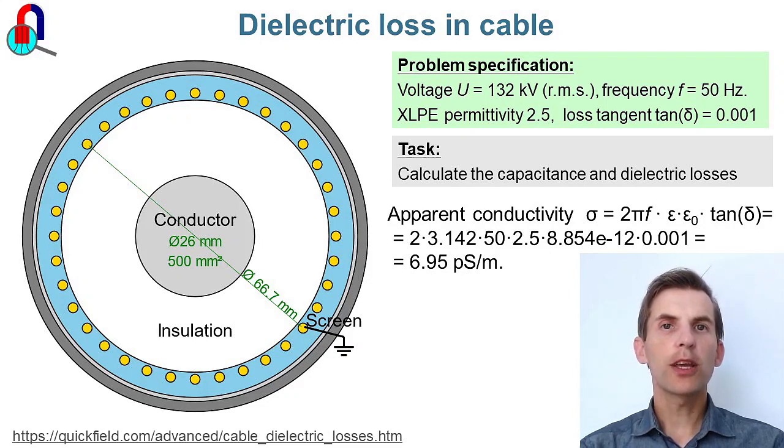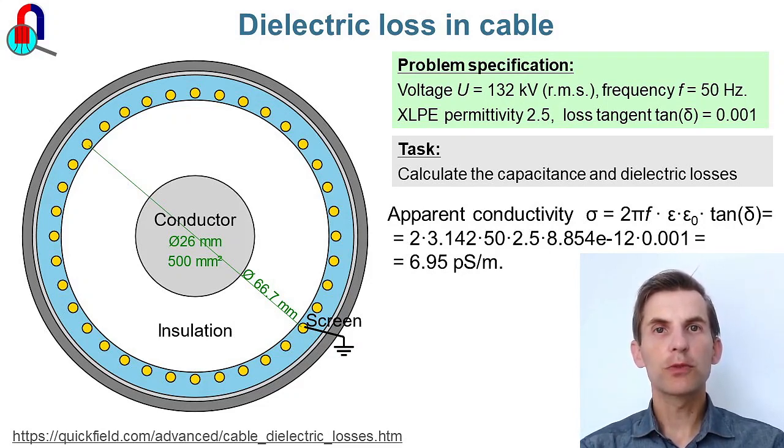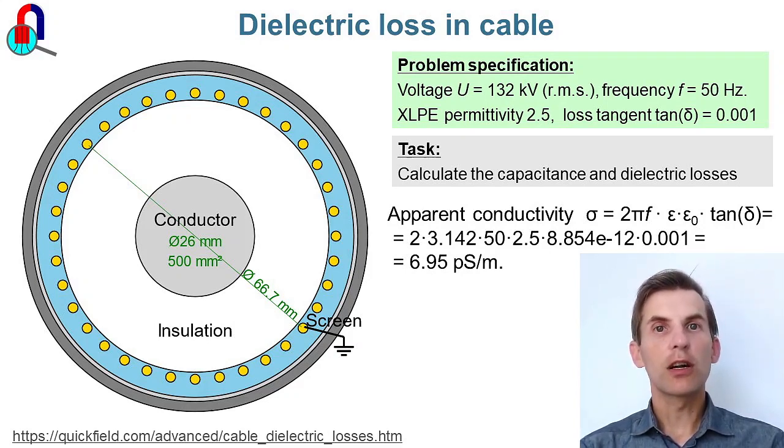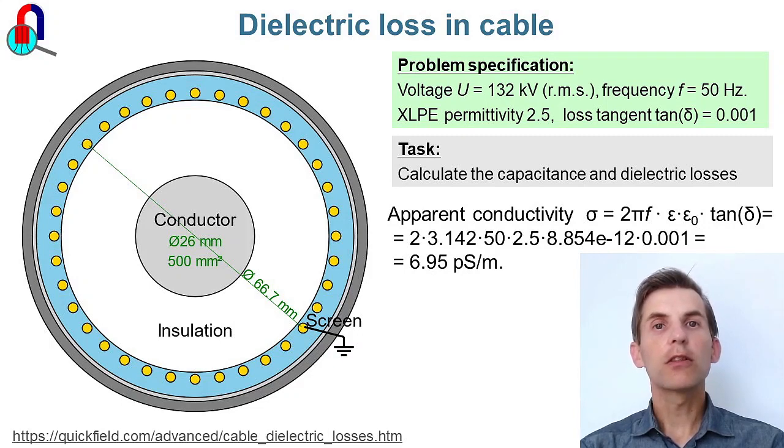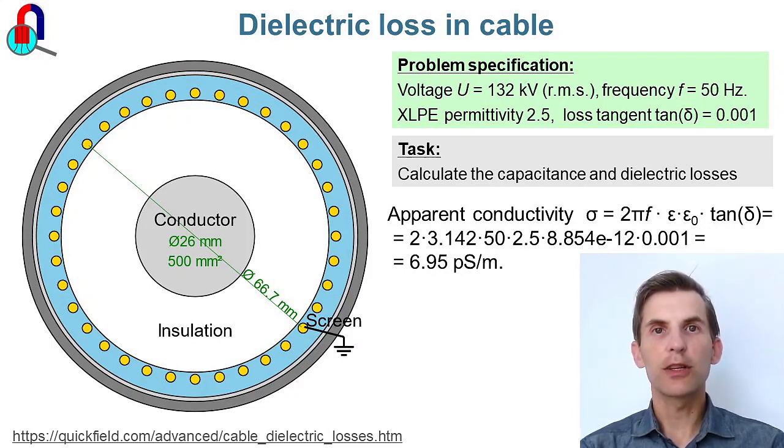The power cable is used to transmit electrical power from the power plant to the load. Even if the load is disconnected and there is no current in the conductor, there are still losses in the cable, the dielectric losses in the insulation.